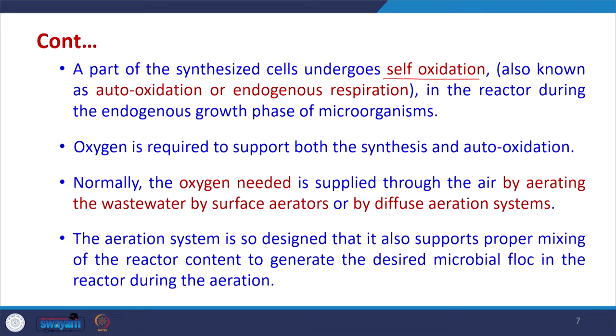Oxygen is required to support both synthesis and auto-oxidation. The oxygen required is normally supplied through air by aerating the wastewater using surface aerators or diffused aeration systems — either may be installed depending on the requirement. The aeration system is designed such that it also supports proper mixing; during the release of air, turbulent mixing happens inside the reactor so that we can generate the desired amount of microbial floc. Aeration along with proper mixing are two essential requirements inside the reactor.